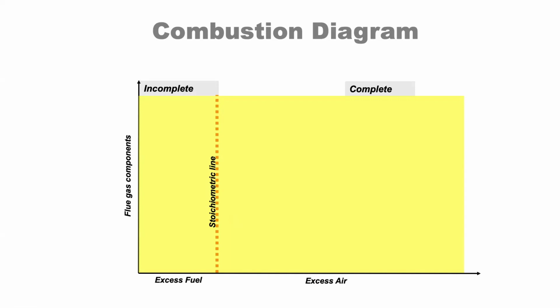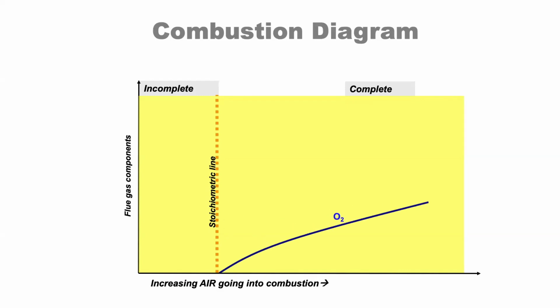You can also think of the left-hand side of having too much fuel and the right-hand side of having excess air. So this would be the amount of air going on the bottom axis, increasing concentrations of air going into the combustion system. Usually do this by measuring oxygen, although there are analyzers. We'll be talking about one, the EOS sensor and the C161 by UEi that actually does measure CO2 and calculates oxygen. Same thing, you can go both ways of the calculation.